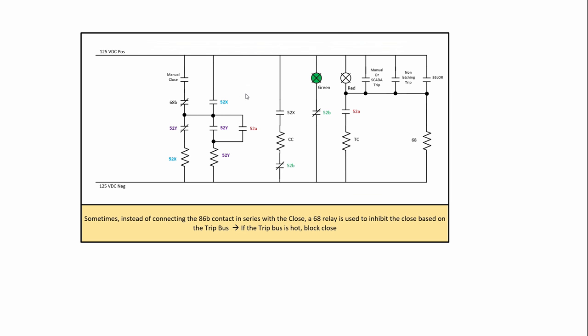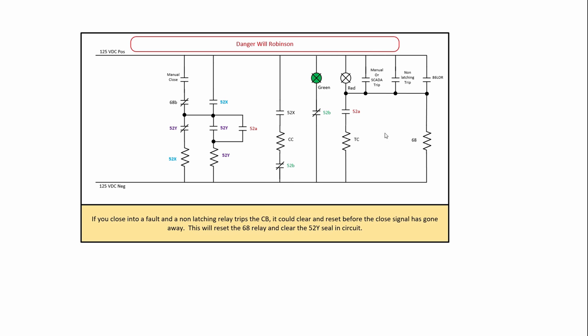So maybe what you decided to do was instead of run a B contact over here to the manual close, you put a 68B and what happens is you take a 68, which is just an aux coil, you pick it up off the trip bus and anytime the trip bus picks up, you then block any closes here. Now, the problem with that would be if this 68 gets picked up momentarily and then you trip back into it or it could get picked up and trip back out from a protective relay that could break this manual closed circuit and null your seal-in circuit and then cause you to reclose.